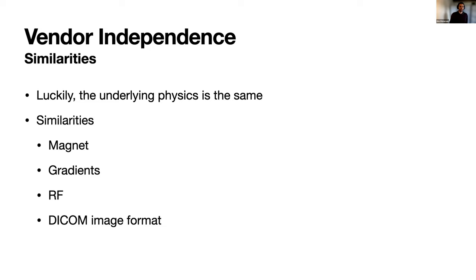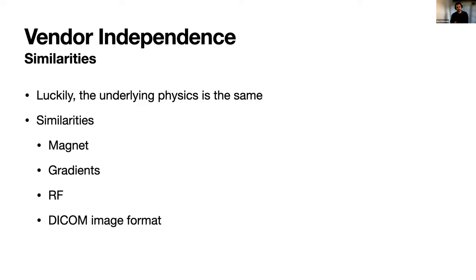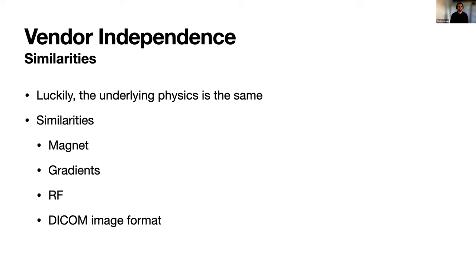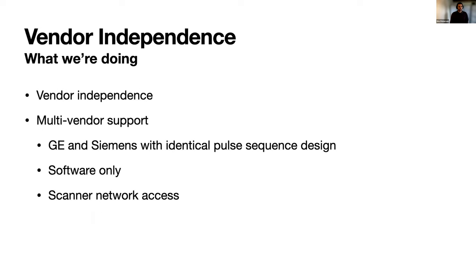Software is maybe more similar within a vendor but very different across different vendors. But luckily, and part of the reason we can be here, is that the underlying physics is all the same. They can't get around that. You have a magnet, gradients, RF coils—that's all you need for MRI. On the output side, the DICOM image format has become the standard to interface with PACS. We have similar inputs and outputs and what comes in between is really what I'm going to be talking about today.